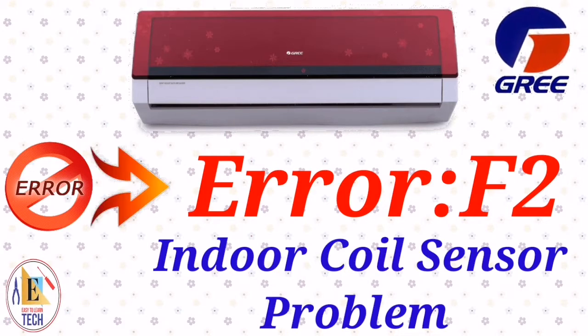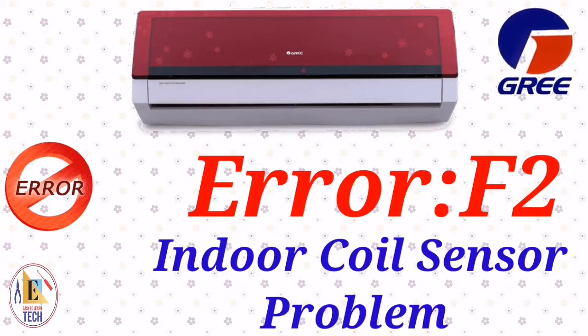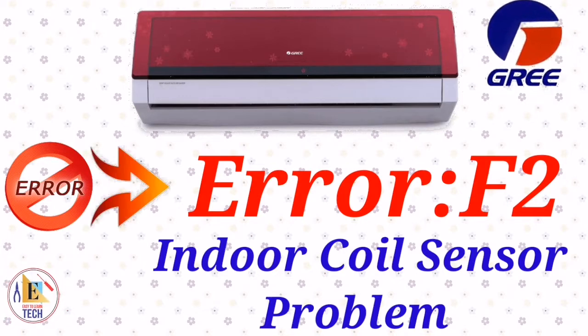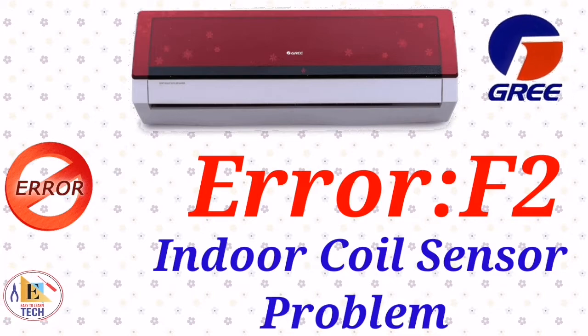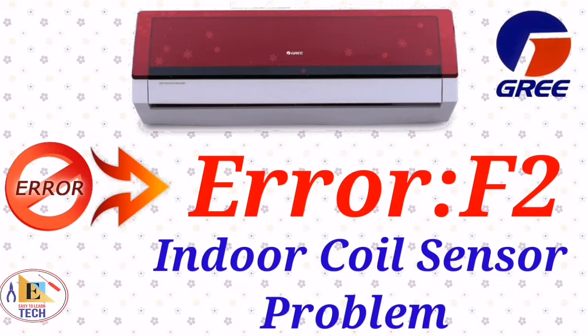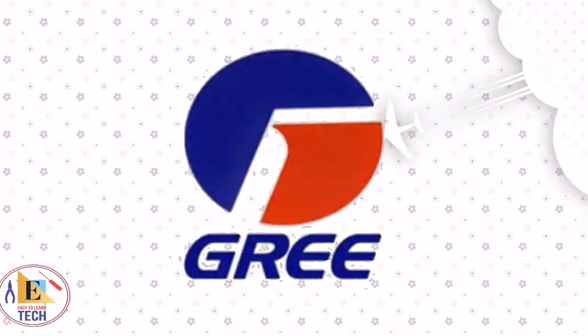And if the resistance is not good, then you have to change the indoor coil sensor. If the resistance is good, then you have to check the indoor PCB. And if the indoor PCB is not good, you have to replace the indoor PCB. Our unit will be in working condition. Let's see the next error code.